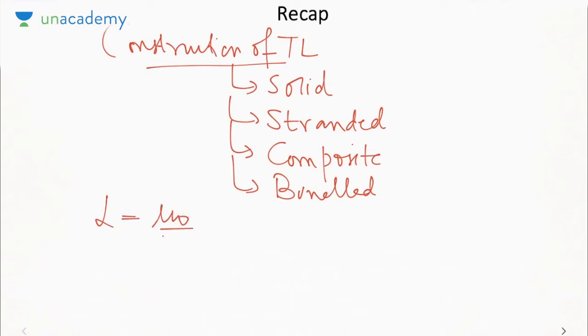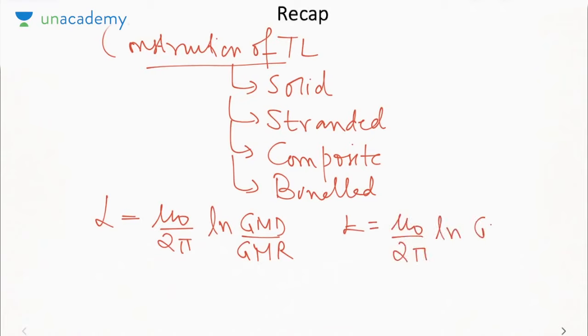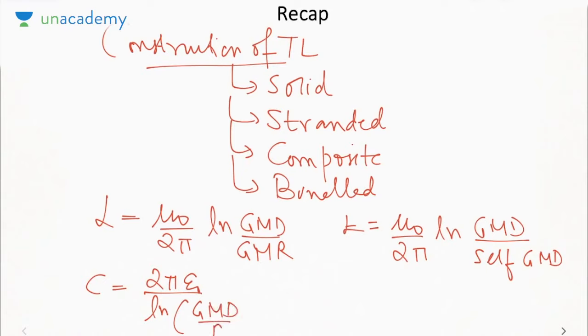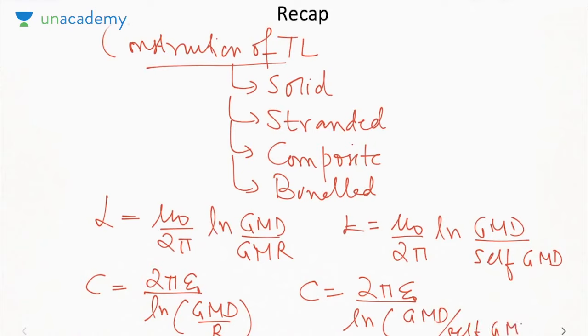Inductance was mu naught by 2 pi ln GMD by GMR for a single conductor system, and it was mu naught by 2 pi ln GMD by self GMD for a bundled conductor system. Similarly, capacitance was 2 pi epsilon naught divided by ln GMD by R for a single conductor system, and it was 2 pi epsilon naught divided by ln GMD by self GMD for a bundled conductor system.